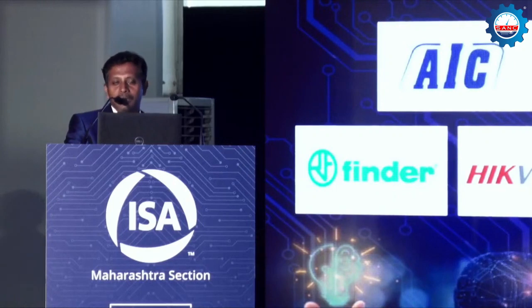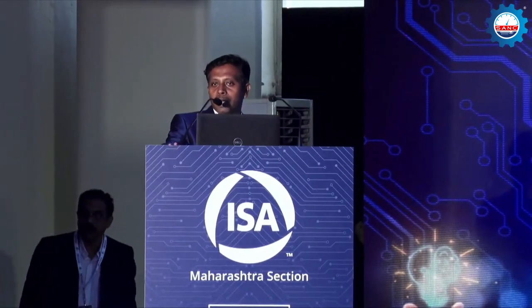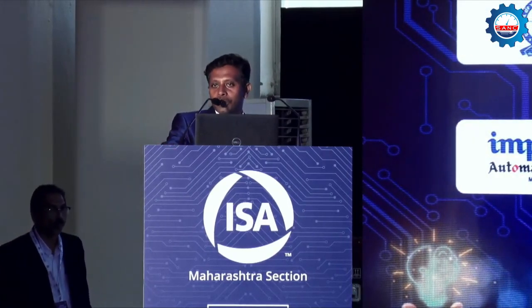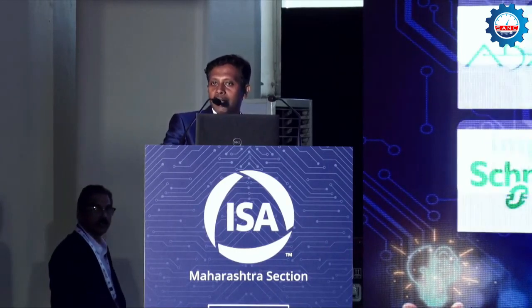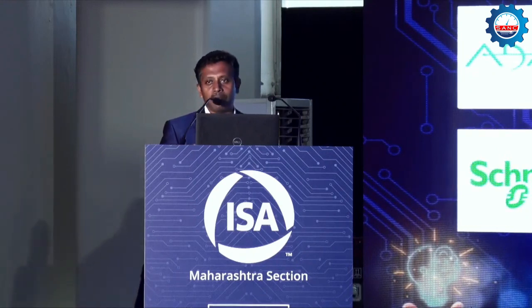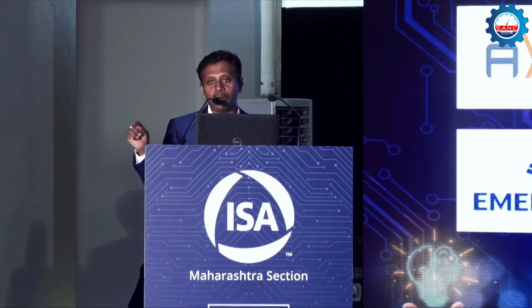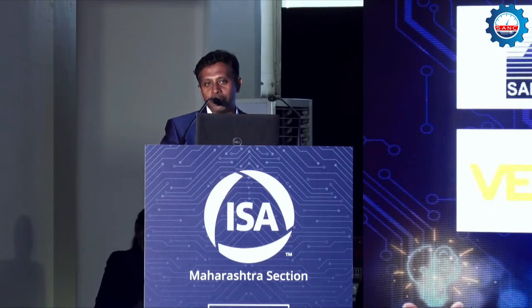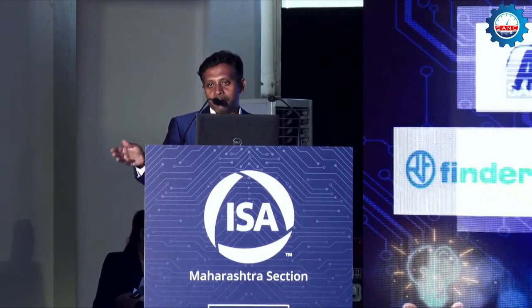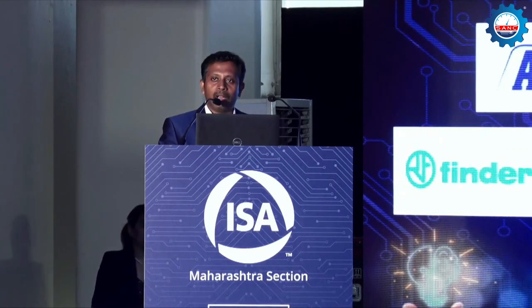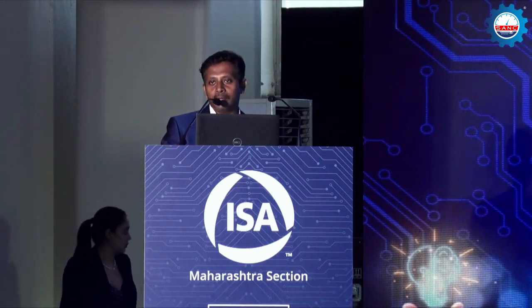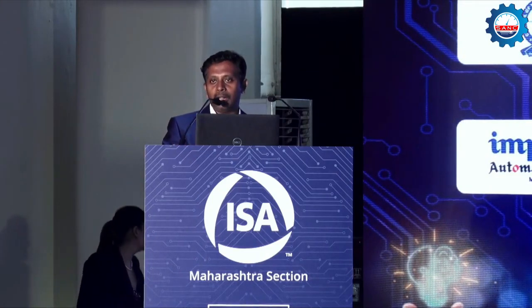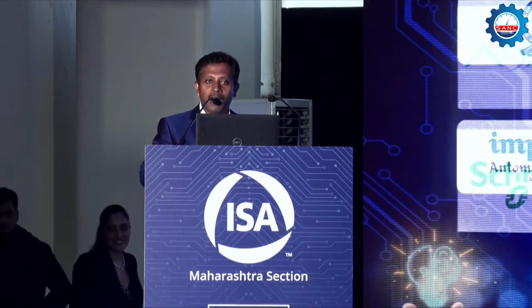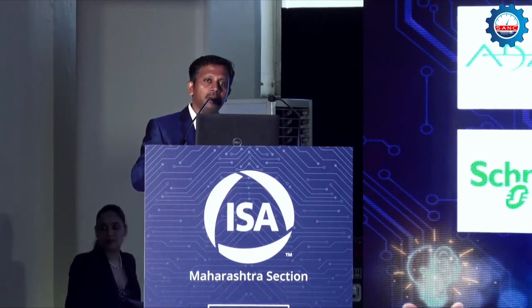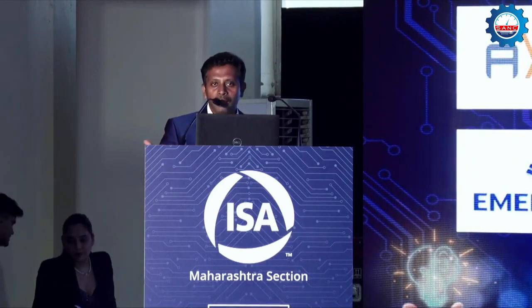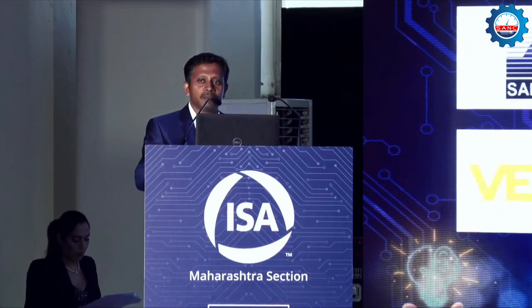The limitation will be on the dielectric constant. For example, if you have a homogeneous medium, where you are not getting different media with different dielectric constants, then there is no issue. Temperature will not have much effect on level measurement because we can dampen the temperature effect. It will have an effect only on the precise measurement of water content. That is the reason we have a density and temperature compensated model. For level measurement, temperature and density will not affect anything. Only the dielectric constant will affect the measurement a lot. You need to have a homogeneous liquid. If you are measuring different liquids in the same vessel, then it is not suitable, and we need a different setup. The dielectric constant should be the same as for the calibration. If you change the liquid to one with a different dielectric constant, then it has to be recalibrated, and then it works. That is the only concern. Hope that answers.